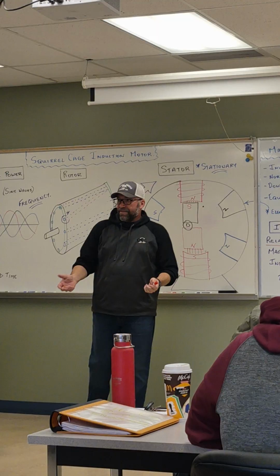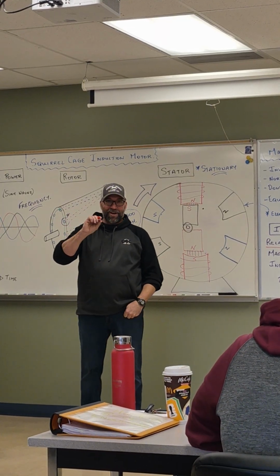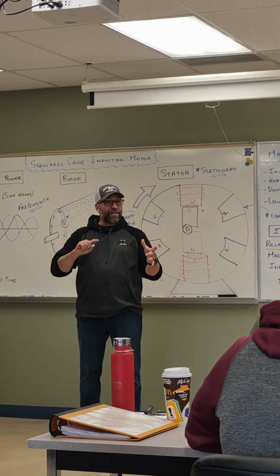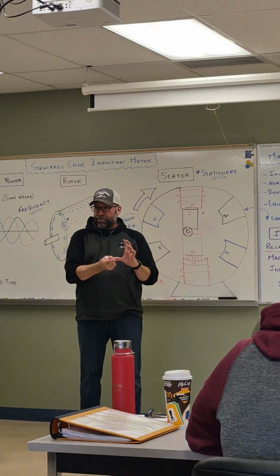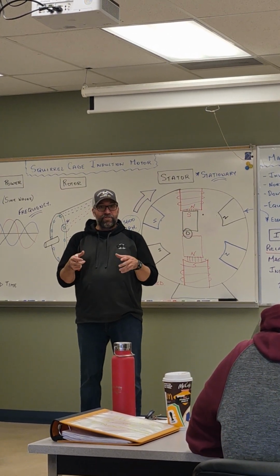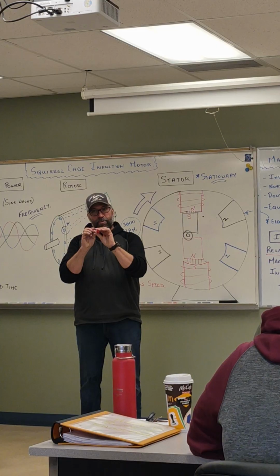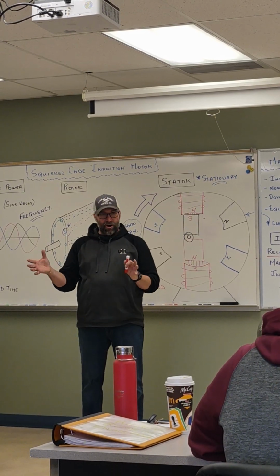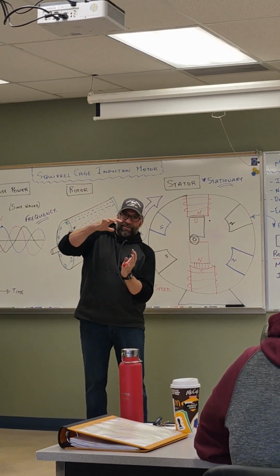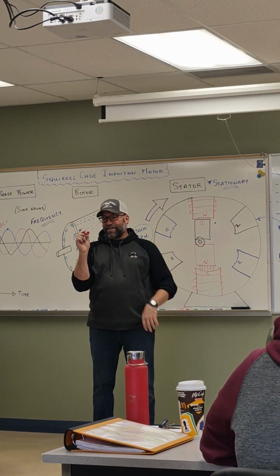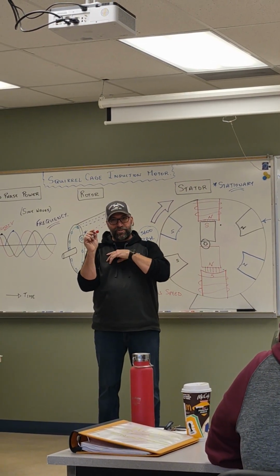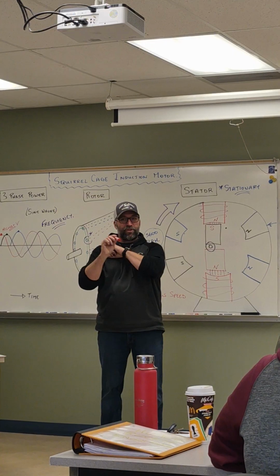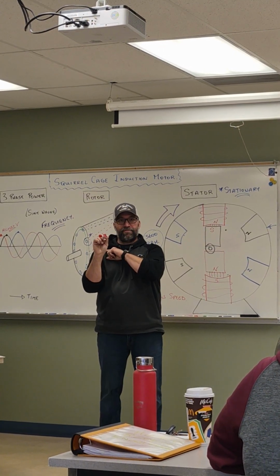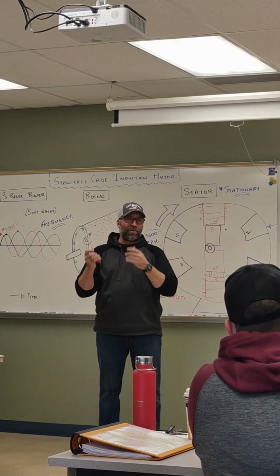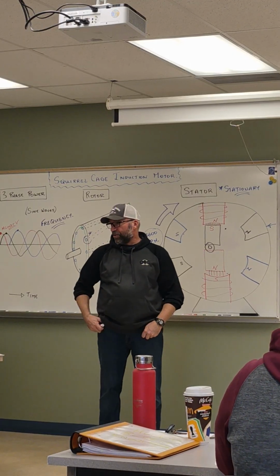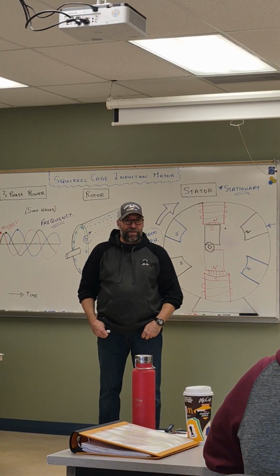It gives us a smoother thrust, like having helical cut gears in a differential versus bevel cut. We skew the rotor bars so that it prevents what's called cogging. By skewing them like that, it's smooth. The thrust happens along the length of it over time instead of all at one time. That's why we angle it, literally for smoother operation. That's it, no other special feature there.